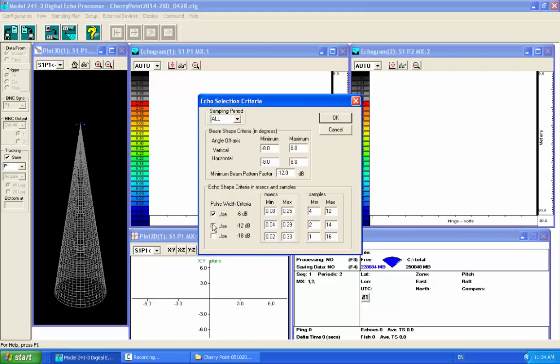But you can collect things wide open, and then as you go through Echoscape, just apply filters and reapply. If you wanted to look at your best echoes for target strength estimation, I might get more stringent on what I accept as a single target echo and limit to the center of the beam, and those would be my best estimators of the fish target strength. But normally when we're collecting data, we want to be pretty liberal about what we let into the data record, because then we have the ability to explore and filter it later, rather than having to go back to those tapes.